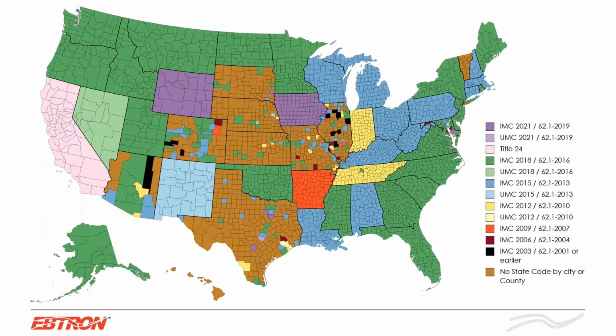And let's take a look at this. So again, I talked about ASHRAE 62.1 a little bit. The IMC and the UMC are really strict interpretations of ASHRAE 62.1. You'll see for Massachusetts, the current design is to IMC 2015, ASHRAE standard 62.1, 2013, but these standards get updated every few years. And it's always really best practice to be designing to the latest standard, because eventually that's going to be updated and accepted in your local building code.